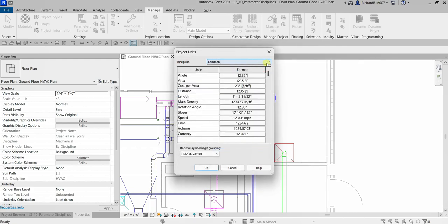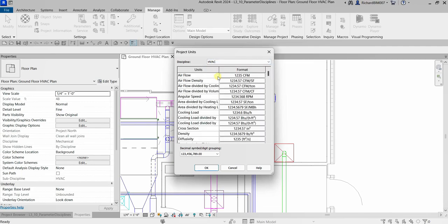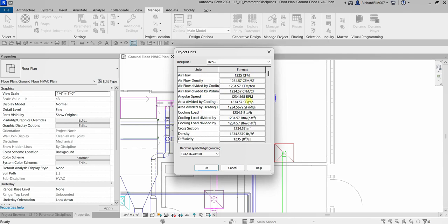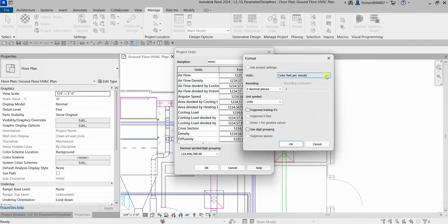If you click the drop-down arrow, you can see the other available disciplines. For example, if I select HVAC, you will see the units under the HVAC discipline. This is why the airflow unit is CFM — it's controlled from Project Units. If I click the format for airflow, you can see it's set to cubic feet per minute with zero decimal places and the unit symbol is CFM. If you want other units for airflow, click the drop-down arrow and specify the unit you'd like.